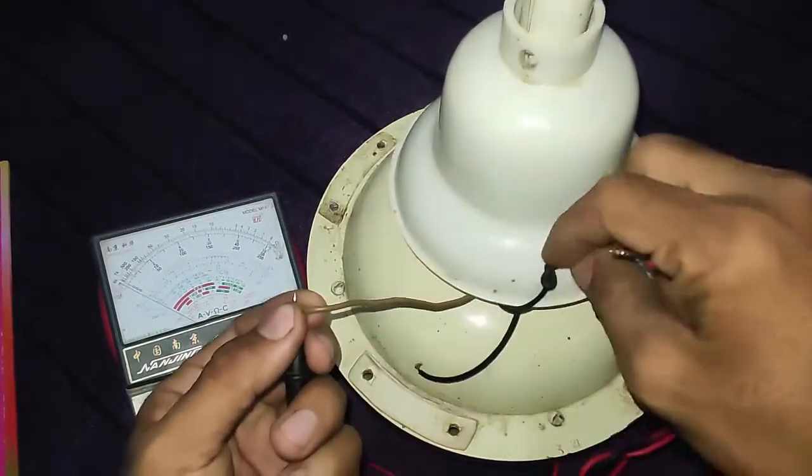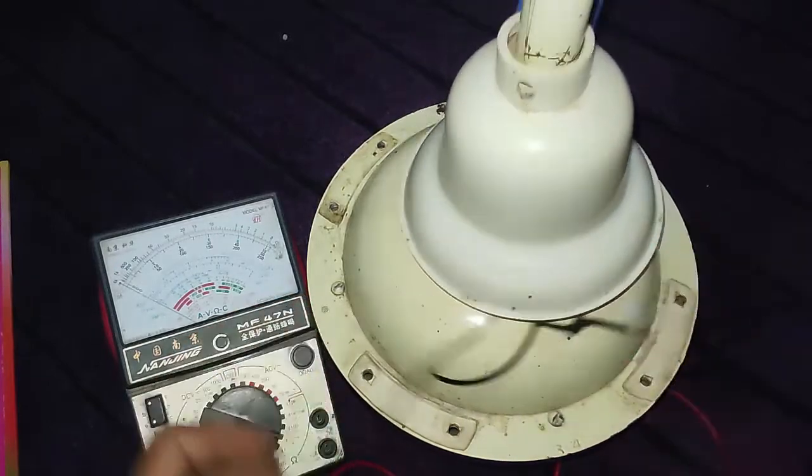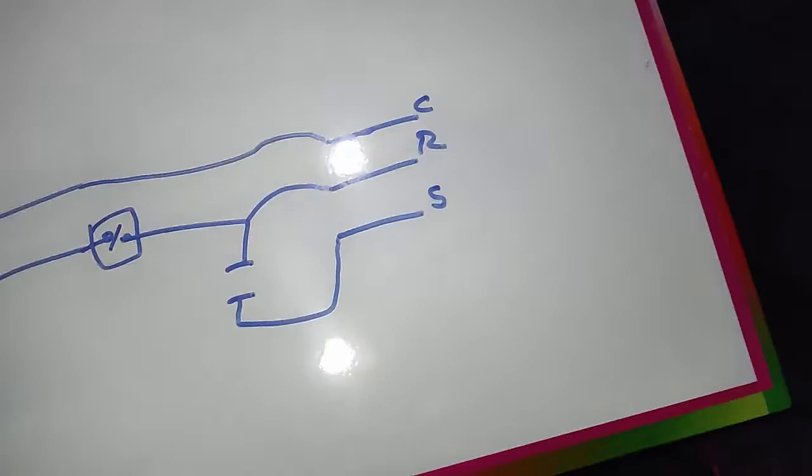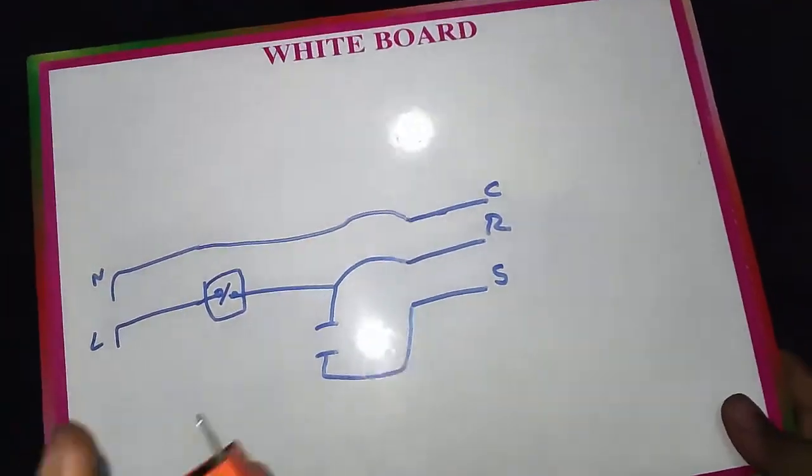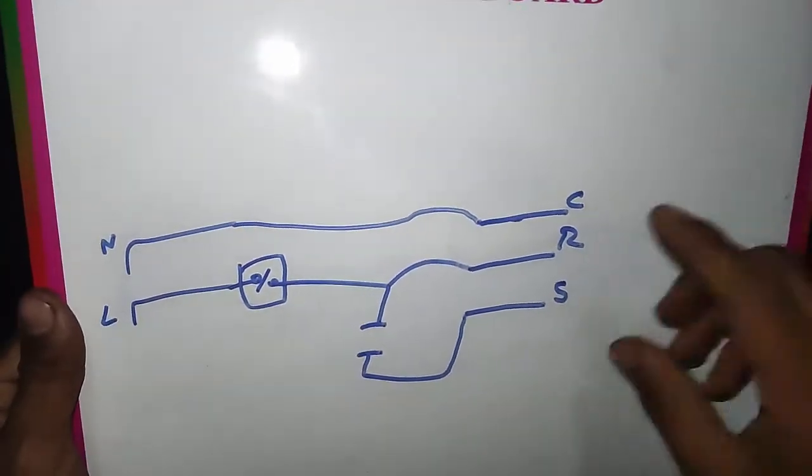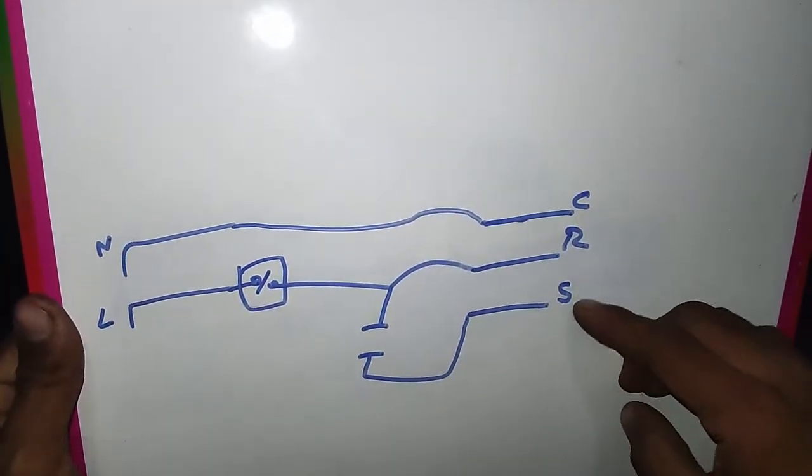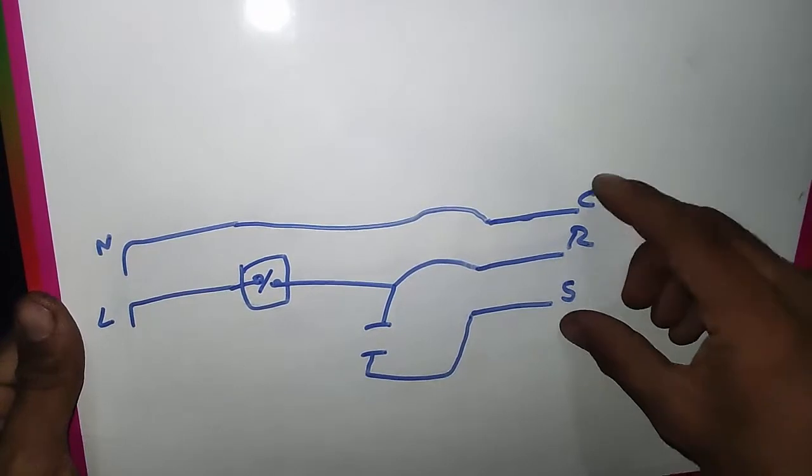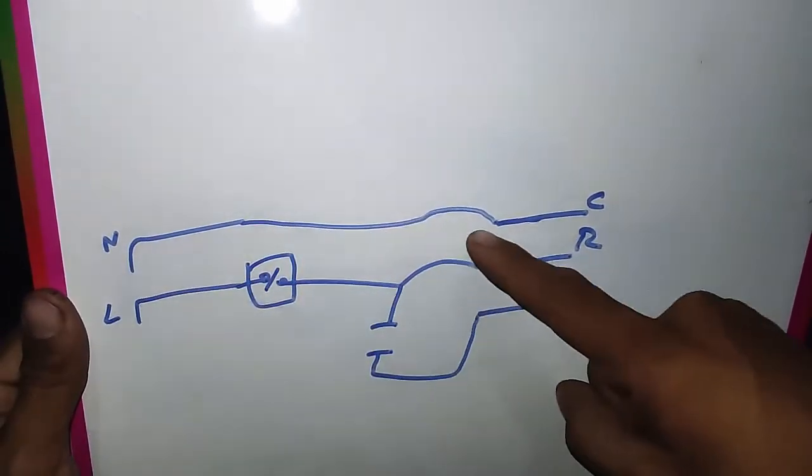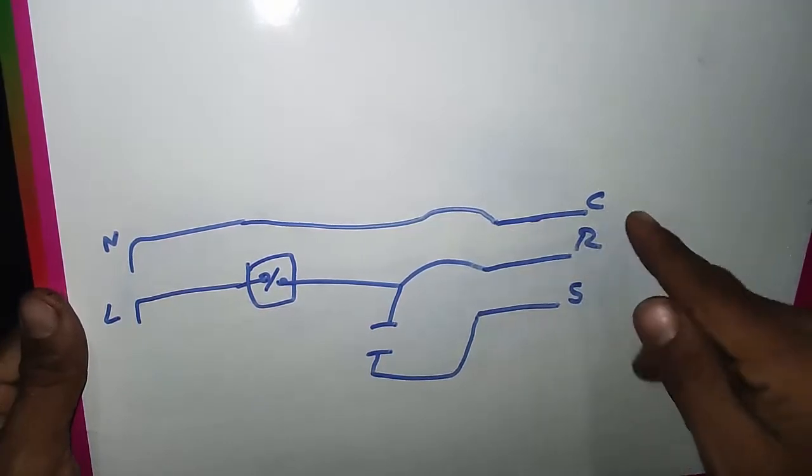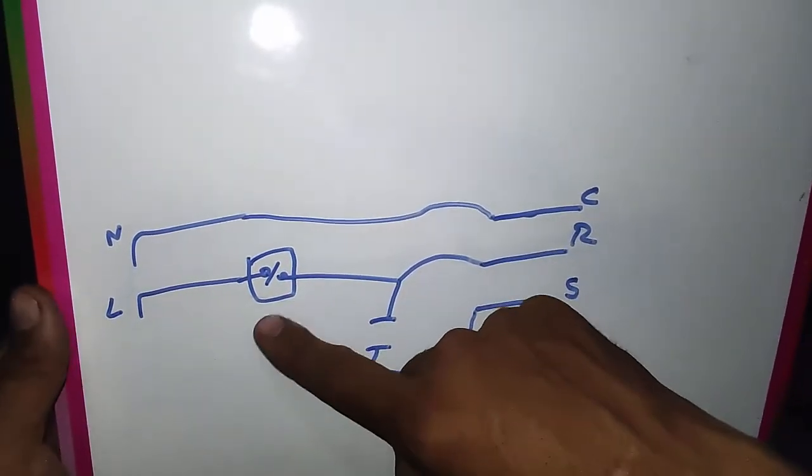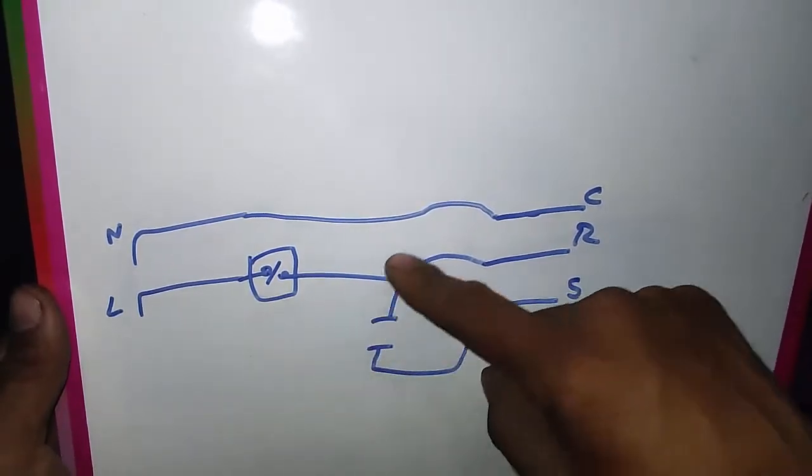Here I show the connection with the capacitor. The 3.5 microfarad capacitor is used with this ceiling fan. I show common, running, and starting terminals as the connection points. The neutral supply goes directly to common, the line supply goes to the one-way switch, and from this switch it goes to the running.